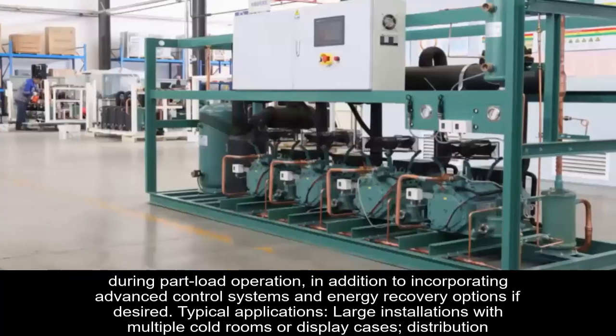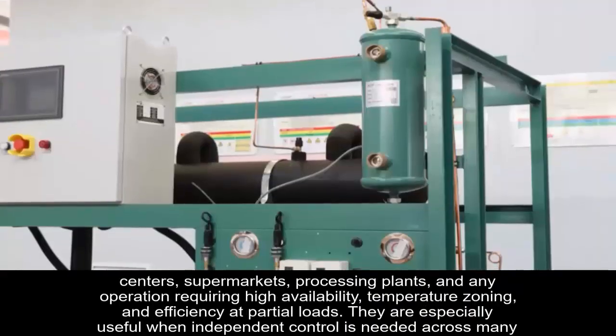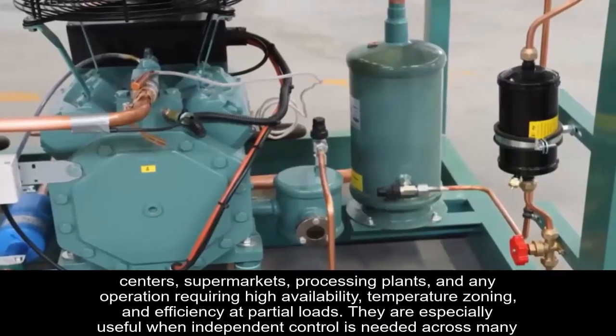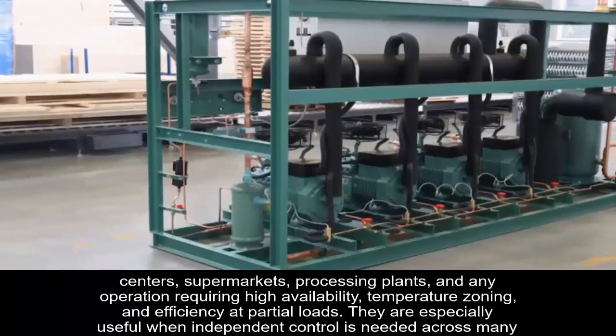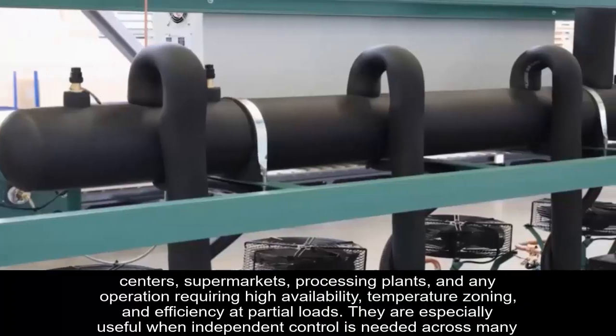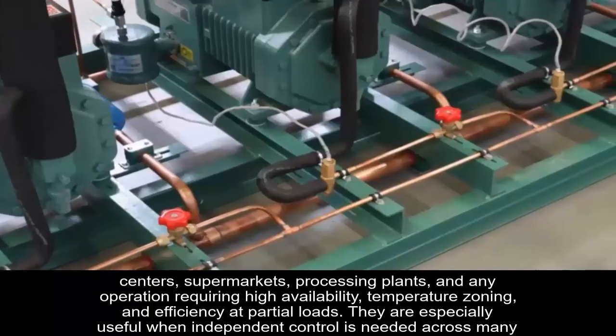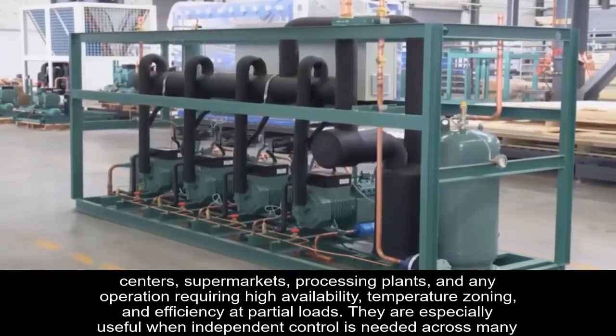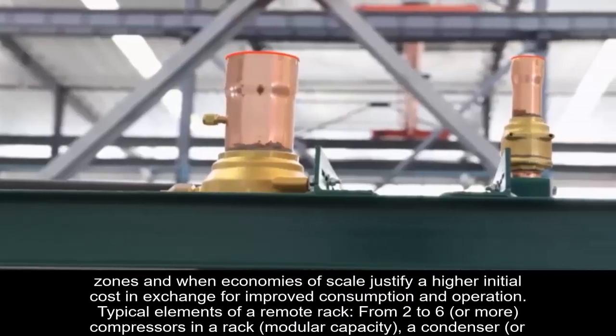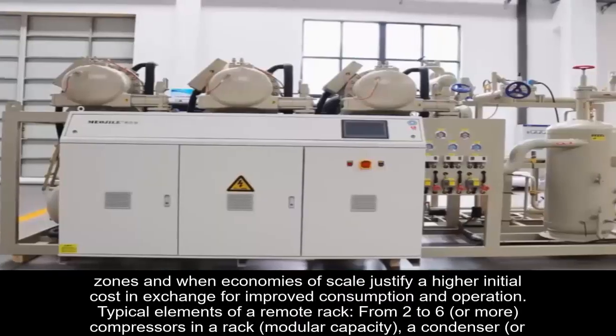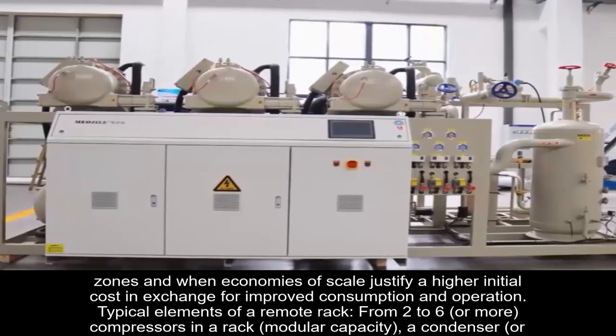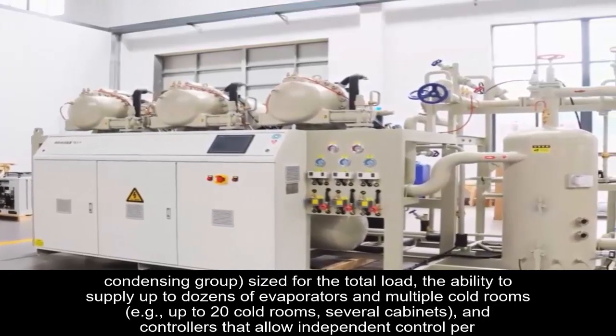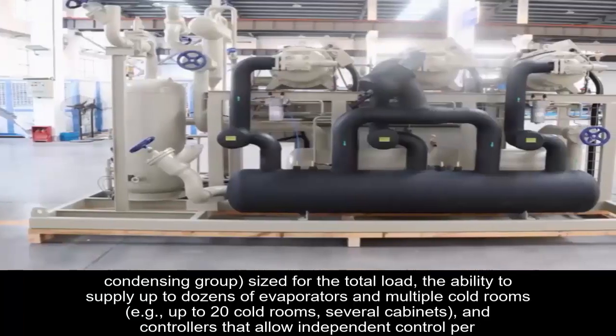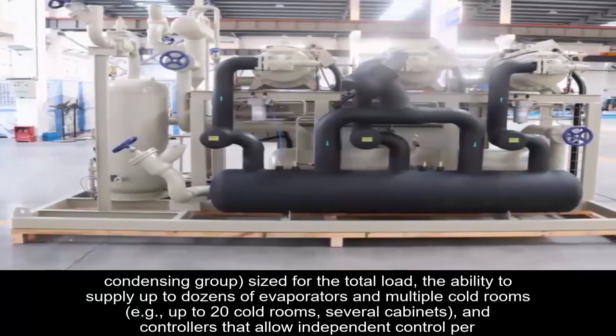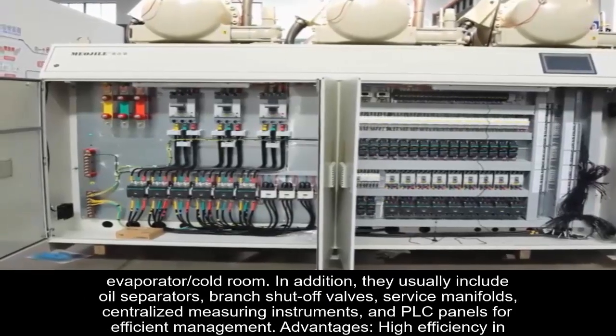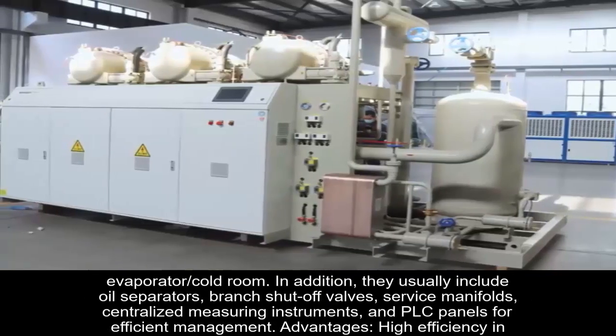Typical applications: large installations with multiple cold rooms or display cases, distribution centers, supermarkets, processing plants, and any operation requiring high availability, temperature zoning, and efficiency at partial loads. Typical elements of a remote rack: from 2 to 6 or more compressors in a rack, modular capacity, a central condenser sized for the total load, the ability to supply up to dozens of evaporators and multiple cold rooms, for example up to 20 cold rooms, several cabinets, and controllers that allow independent control per evaporator or cold room.